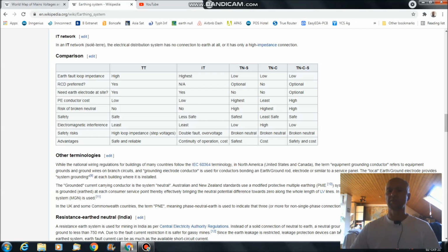In the TNCS, you see it's optional, but here some countries mandate installing an earthing electrode at your site. Some countries, probably in the United States, will be like that. One commenter wrote that an earthing electrode is only required for lightning protection by his code, so why should he put one when installing an inverter? So some countries mandate it, some don't, but that's only when you talk about grid connection.